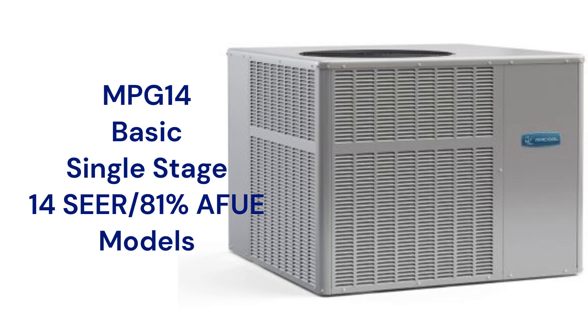The units use aluminized steel tubular heat exchangers, which resist corrosion, but they are not as durable as brands that use stainless steel construction.